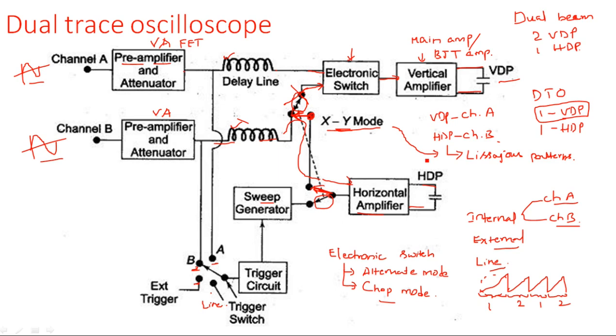To summarize the dual trace oscilloscope: only one set of vertical deflection plates and one set of horizontal deflection plates are used. The single set of vertical deflection plates displays both signals using an electronic switch, which operates in two modes — alternate mode and chop mode. In alternate mode, Channel A is selected during the first sweep and Channel B during the second sweep, alternating. In chop mode, signal samples are rapidly selected and transmitted to the vertical deflection plates. In XY mode, both plates are operated with sinusoidal signals and Lissajous patterns are generated on the display.